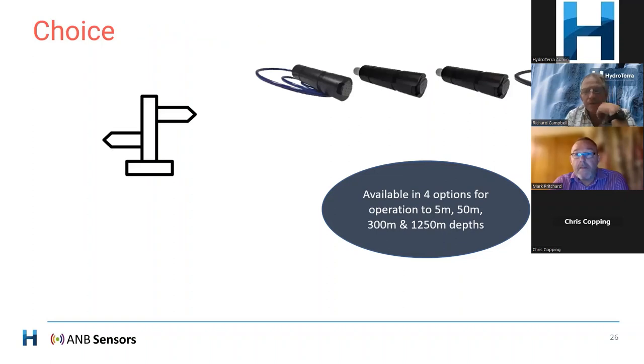Going back for a sec - that submergence depth of 1,250 metres is very significant versus traditional pH sensors. What's the sort of maximum depth you see traditional pH sensors coming down to - is it about 300 metres? There are some, if you go into the oceanographic side, that will go down to 2,000 metres, but the price of those units is more than three times the cost of ours, and they need calibration, which takes about 3 months. So it's a very, very different ballgame.